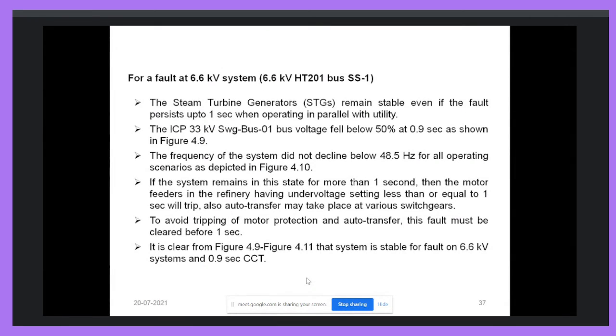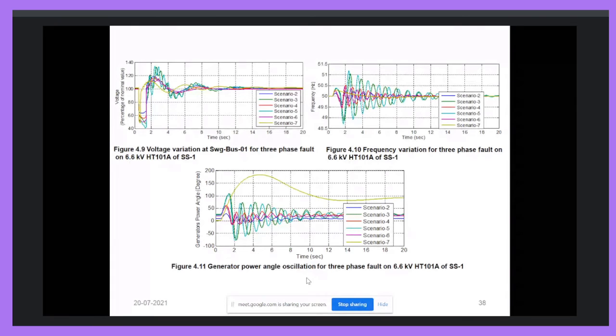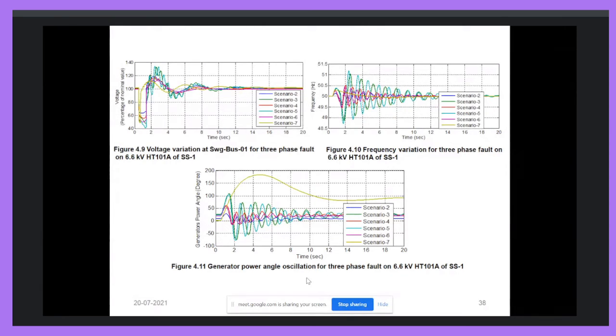These are the results for the 6.6 kV fault, the fault on the 6.6 kV distribution system. Here you can see in case of the 33 kV system, the voltage was 0. When the fault occurred in a 33 kV system, voltage became 0. But in case of the fault which occurred in a 6.6 kV system, the voltage is not 0. It is around 50% of the rated voltage, and the frequency deviation is also less as compared to the fault which occurred on the 33 kV system.